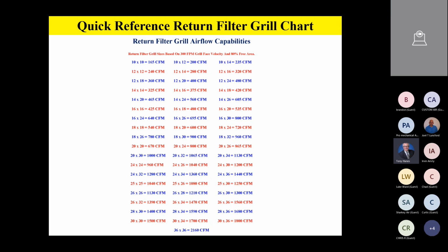We've all been on calls where the return air grill would be singing, and what causes that is too high face velocity. Joel has this at 300. In the manuals published by the grill manufacturers, you'll find different recommendations on face velocities for different applications, and so that's real helpful.